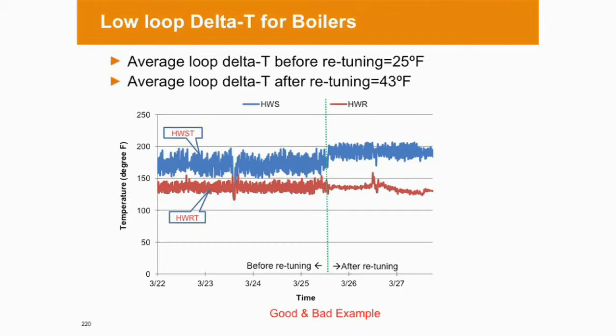I apologize, it needs to be fixed. I keep saying that. But if I'm resetting, I'm not going to raise, the blue line is my supply temperature. I'm not going to increase the supply to get a wider delta. What you can see, it's just for demonstration purposes that we show a tighter delta, and after readjusting, we want to get that difference between what's going out from the hot water loop, the boilers, and the return coming back.